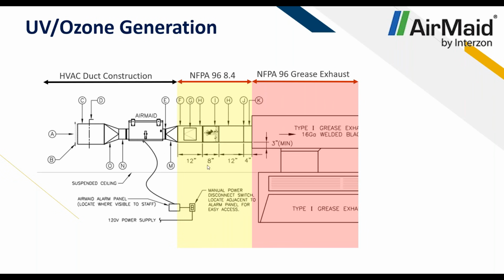So here, just a little bit more of some pictures of it. We'll have some construction with the AirMaid, getting that bleed airflow and sending it in. We also have some fire smoke dampers in here as well to prevent anything going back in. In the event of a fire, we'll completely shut this off and make sure that we're not sucking in air as the fire occurs.